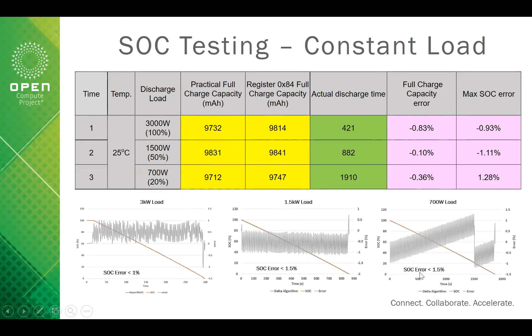When we use a constant load to do the SOC check, we discharge at 3 kilowatts, and the SOC error is less than 1%. With a 1.5 kilowatt constant load, the SOC error is less than 1.5%. With a dynamic load from 62 amp to 31 amp every 3 seconds, the SOC error can be maintained at less than 1%.